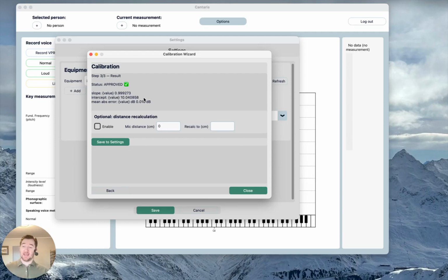What if you don't reach that below 1 decibel threshold and it's bigger than 1 decibel? Well, things that you can look out for is, have I really selected the right microphone? Have I read my decibel meter right? Has my colleague read the decibel meter right? Because the sounds are a little bit finicky and they change a lot. And also, did I make sure that my room is quite silent? A lot of background noise is going to disturb this process a little bit. And you can just do it again. Now, if you've done this all several times with a colleague and things are not working out, just reach out to us and we can give you some more advice in this calibration process.